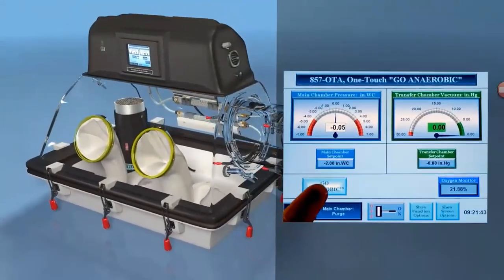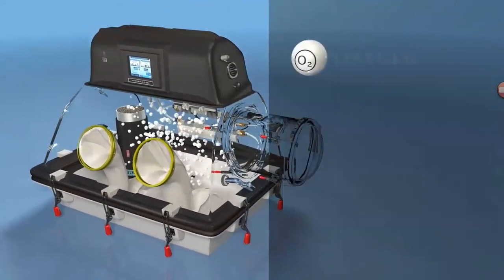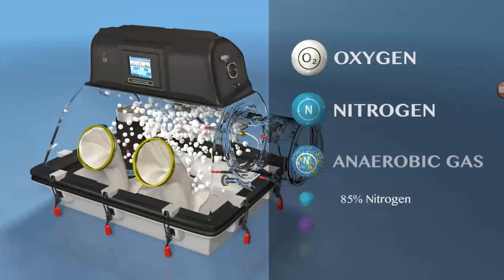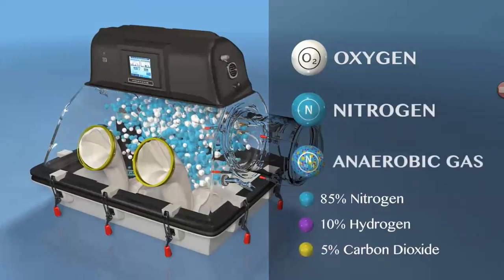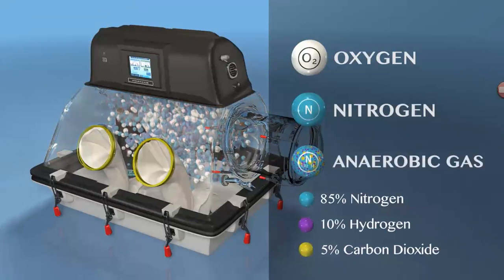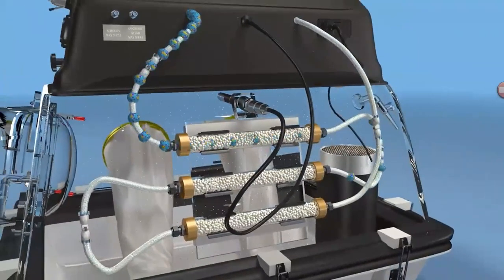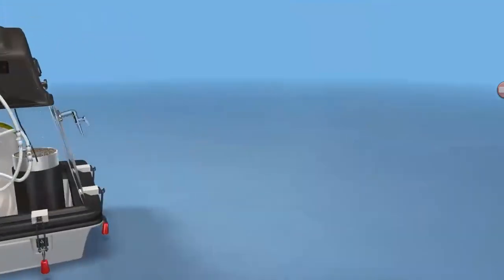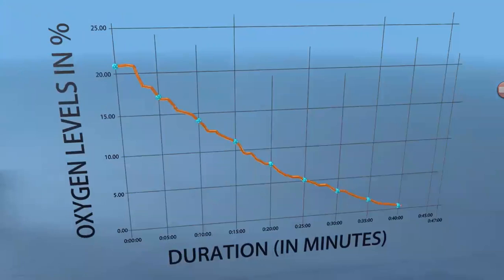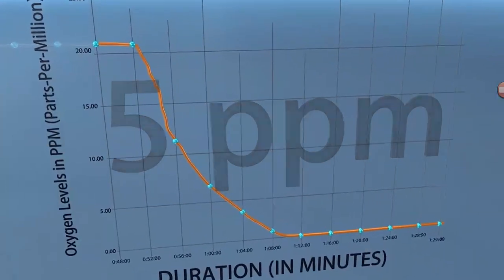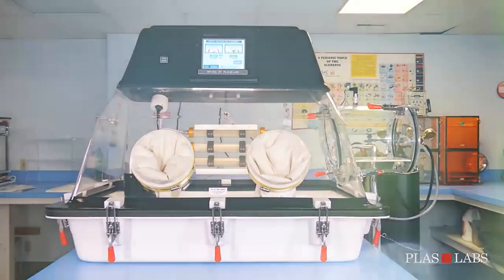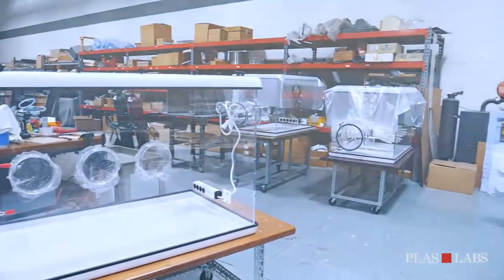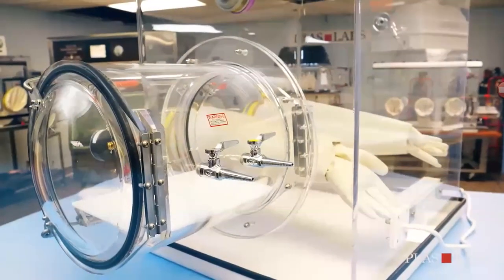During the Go Anaerobic operation, the first 4 purge cycles use nitrogen gas. After the 4th cycle, the PLC switches to anaerobic gas. The PLC will continue this purge sequence until the oxygen levels are below 5 parts per million. Approximately 27 purging cycles make up the Go Anaerobic operation. Upon completion, purging the anaerobic chamber, less than 300 liters of gas will be consumed. The completely sealed design reduces the amount of gas needed to purge and maintain the anaerobic chamber. Your anaerobic chamber is now ready to use. Be sure to visit plaslabs.com to view our state-of-the-art isolation and containment glove boxes.